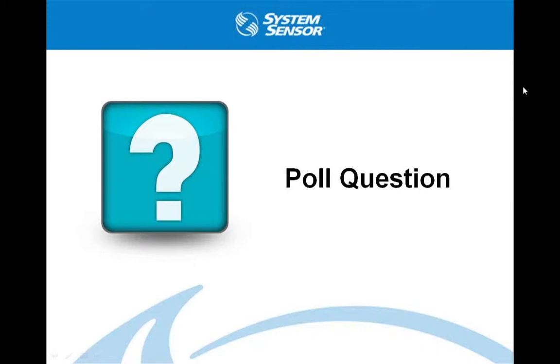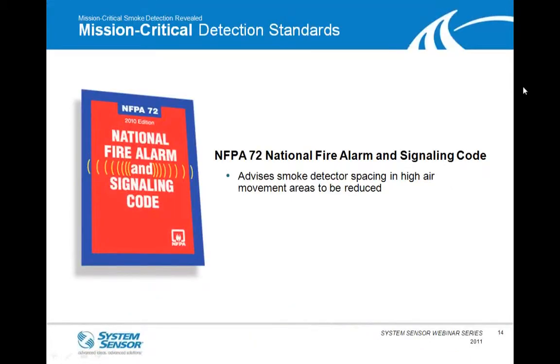All right, great. Again, that poll question was more of a precursor to just kind of see where everyone stands. The answer to that question actually is none of the above. And we're going to go through each one of those standards in a little more detail. It's a kind of a misnomer that a lot of people think, especially NFPA 76, calls out the requirement for aspiration. The fact of the matter is none of the three specific call out the use of aspiration, but rather if aspiration is used, here's the standard, here are the requirements that you have to meet. So that's kind of the caveat.